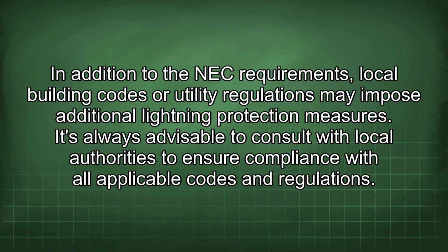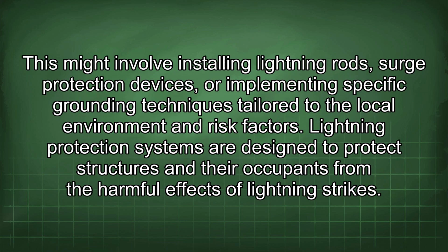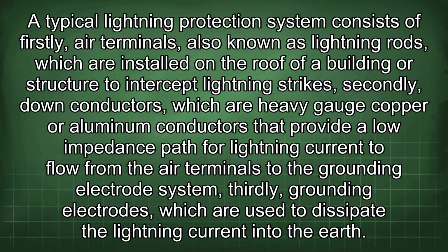In addition to the NEC requirements, local building codes or utility regulations may impose additional lightning protection measures. It's always advisable to consult with local authorities to ensure compliance with all applicable codes and regulations. This might involve installing lightning rods, surge protection devices, or implementing specific grounding techniques tailored to the local environment and risk factors. Lightning protection systems are designed to protect structures and their occupants from the harmful effects of lightning strikes. A typical lightning protection system consists of, firstly, air terminals, also known as lightning rods, which are installed on the roof of a building or structure to intercept lightning strikes.